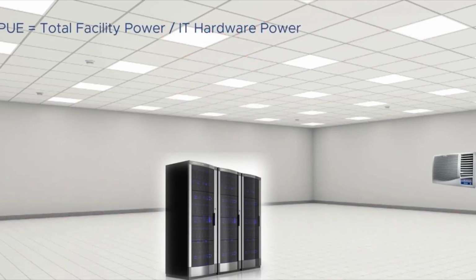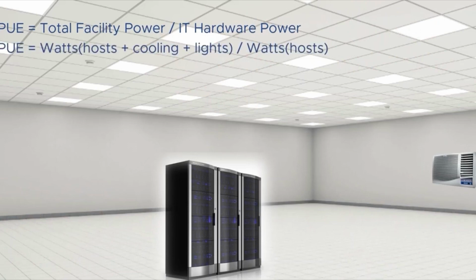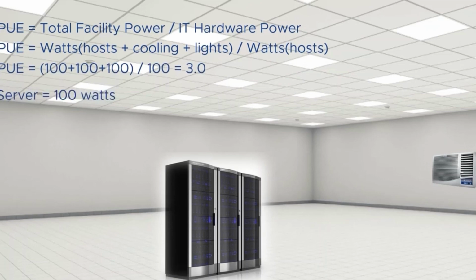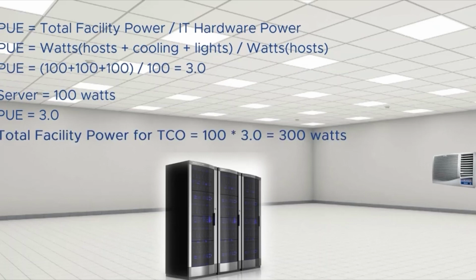So to calculate the PUE, we would have the total facility power divided by the IT hardware power. In this case, we have the wattage for the host, the cooling, and the lights divided by the wattage for the host. We have 100 plus 100 plus 100 divided by 100, which gives us a PUE factor of 3.0. So, if we know that the server takes 100 watts, and we know that our PUE factor is a 3, then we know that the total facility power for our TCO will be 300 watts.